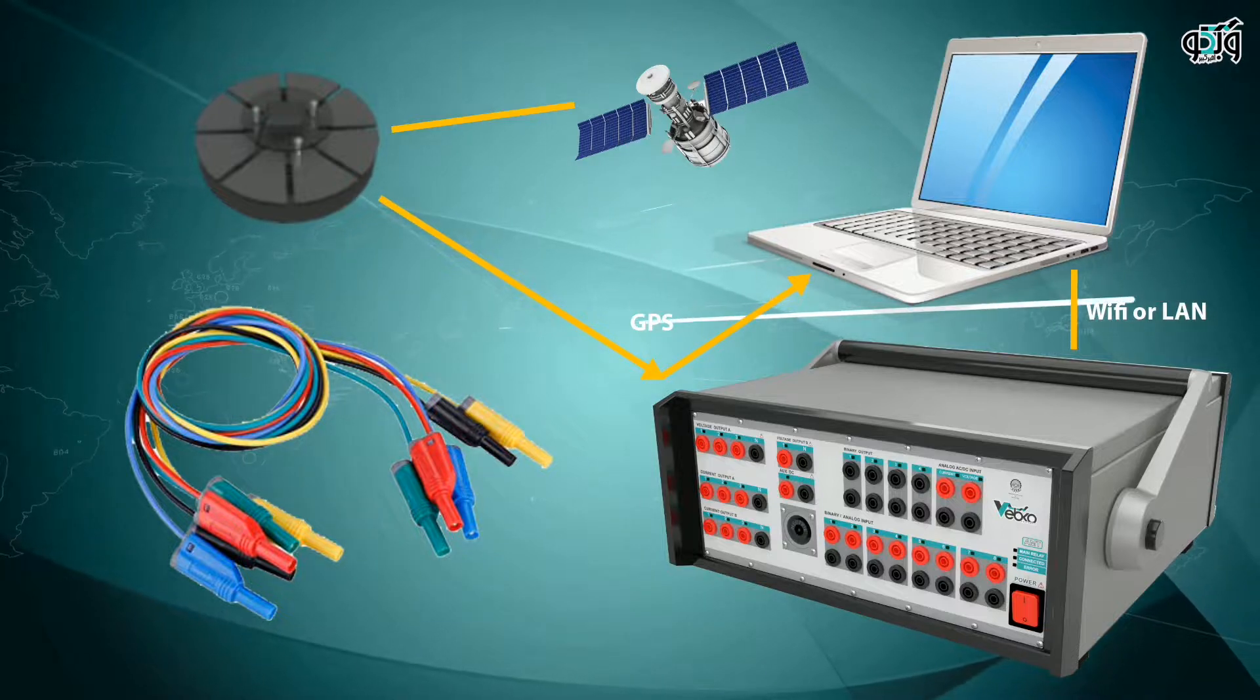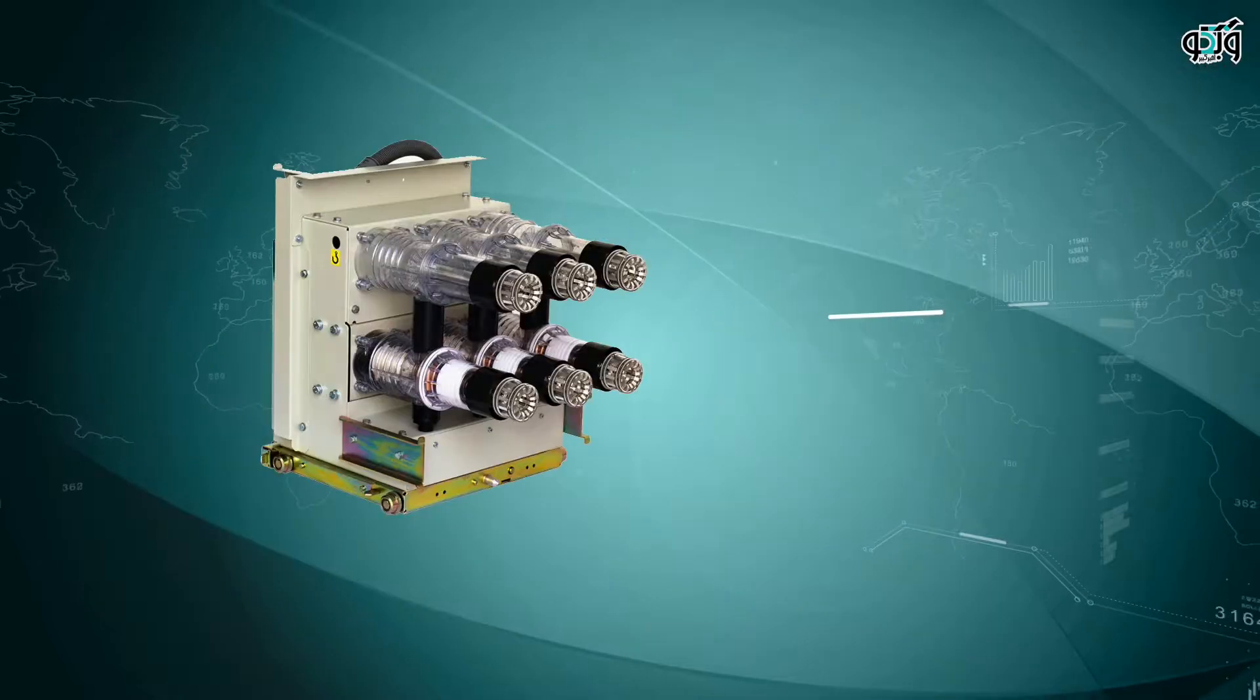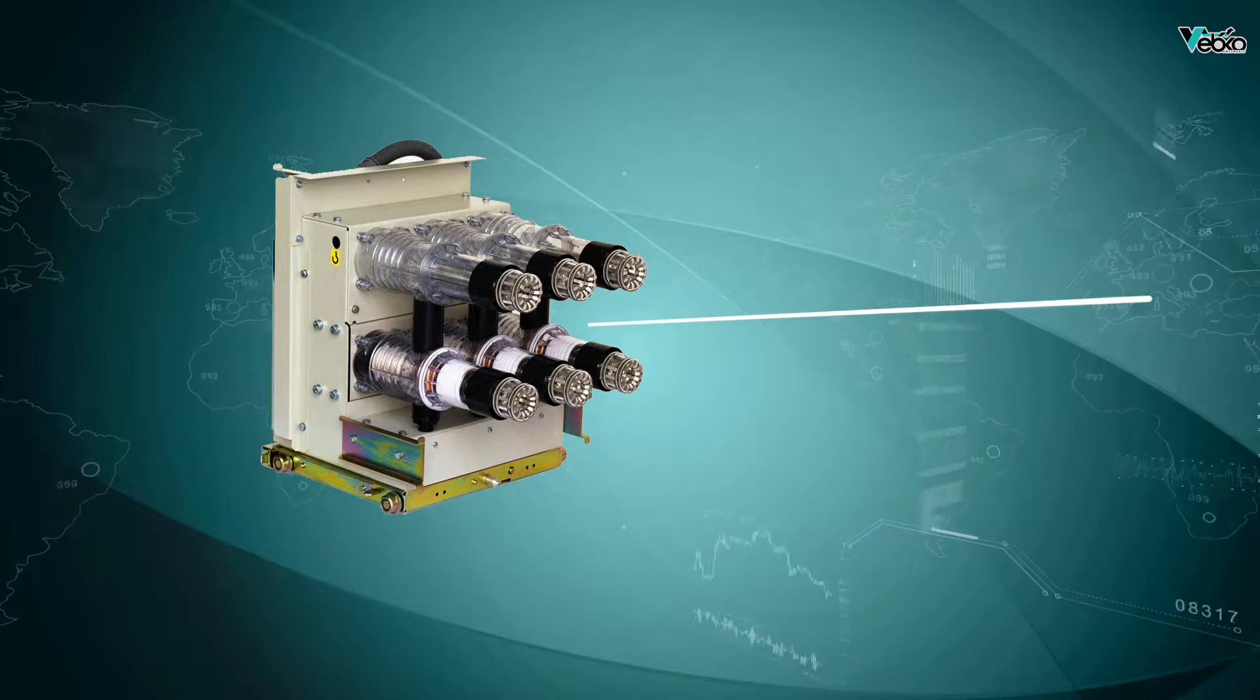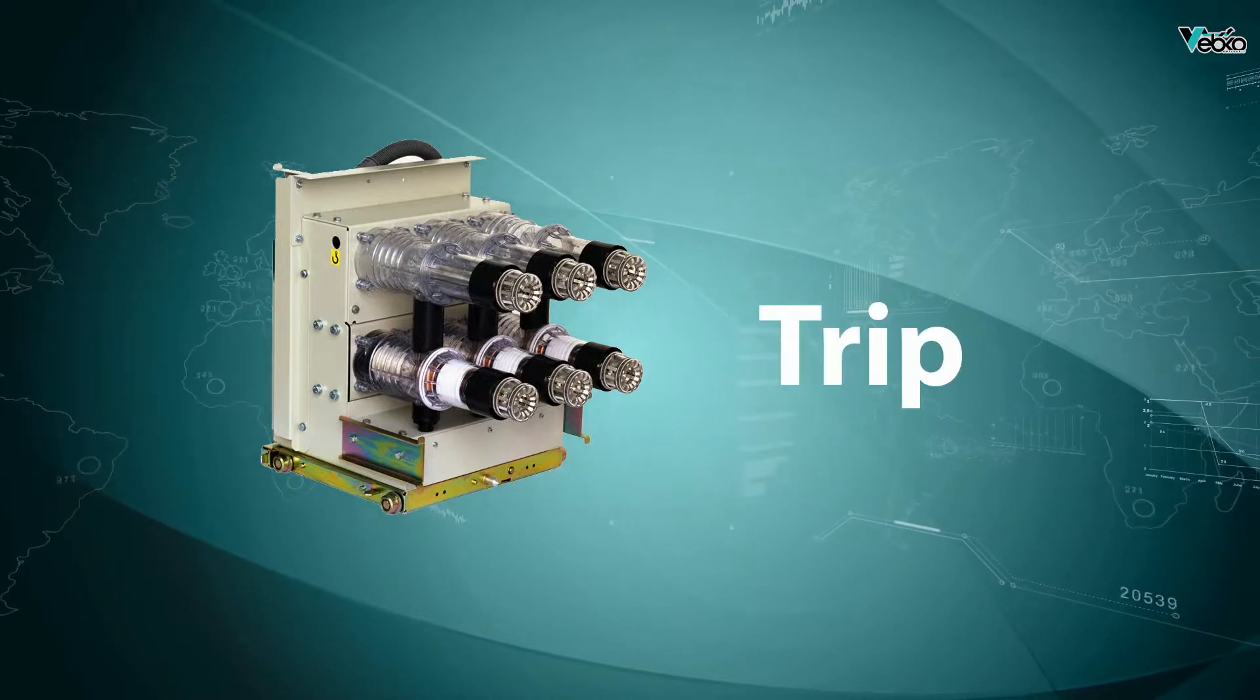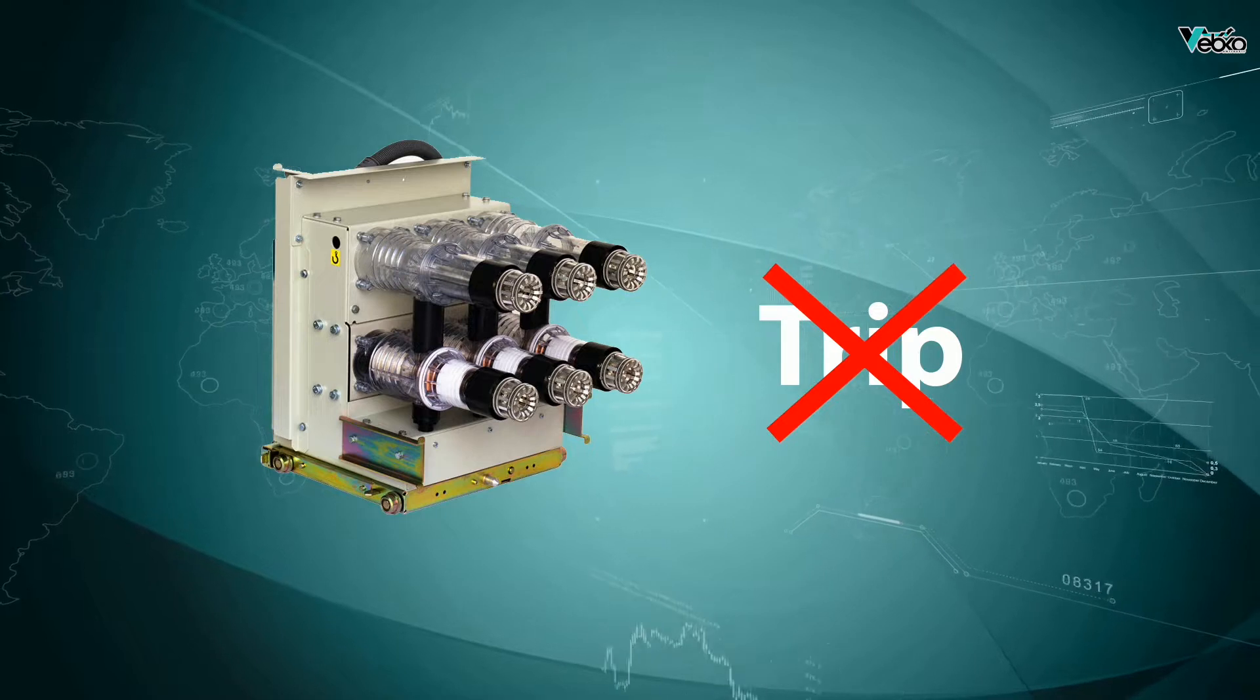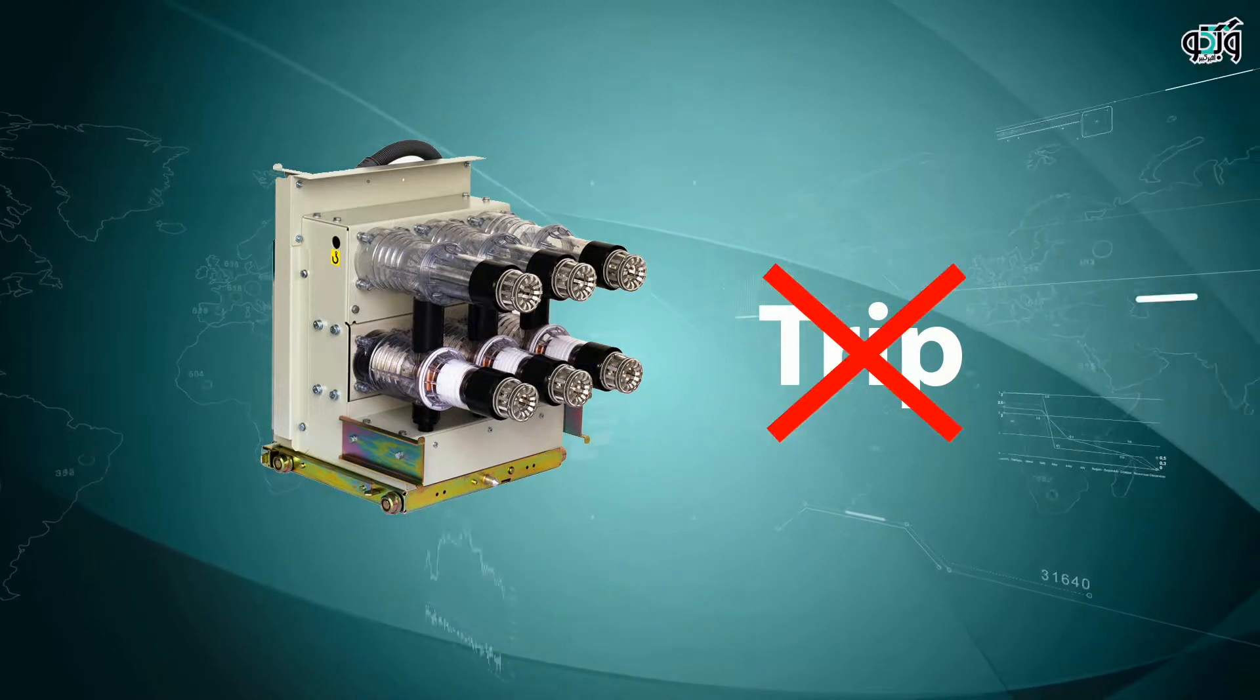To make sure that the breaker contact position is properly simulated by the test device, put the breakers in the right position. It should be noted that if other groups are working on the circuit breaker simultaneously, it is necessary to use the test block to make sure that no trip is going to go on the circuit breaker.